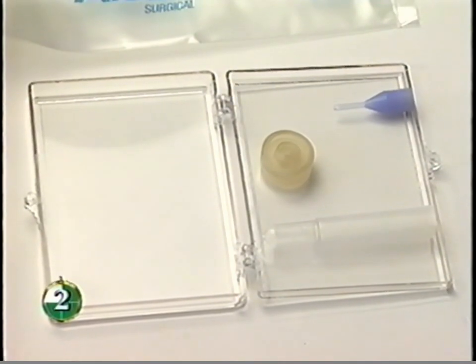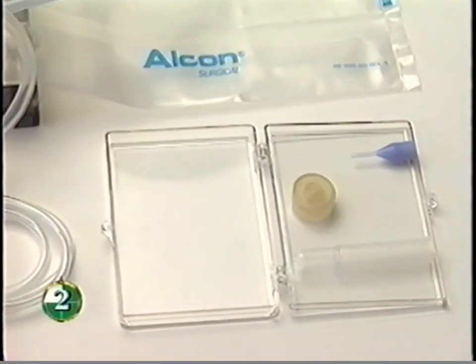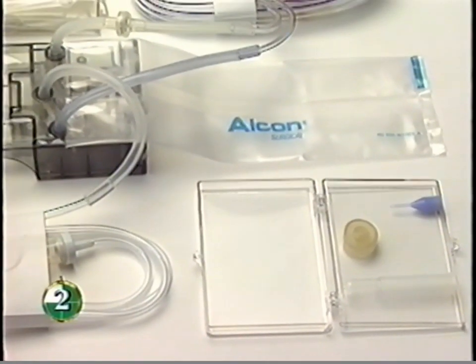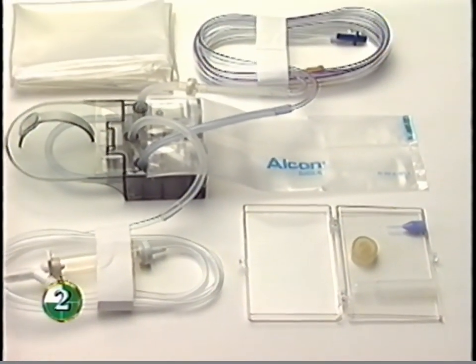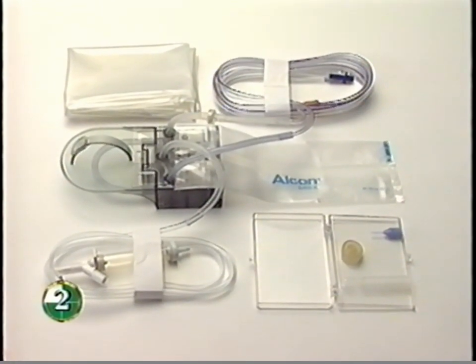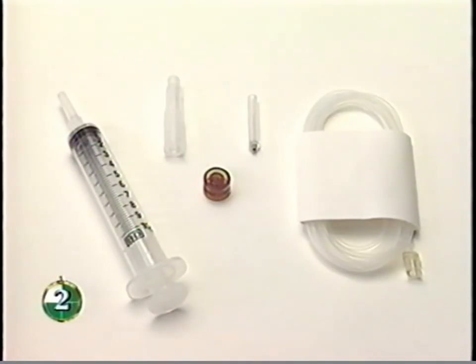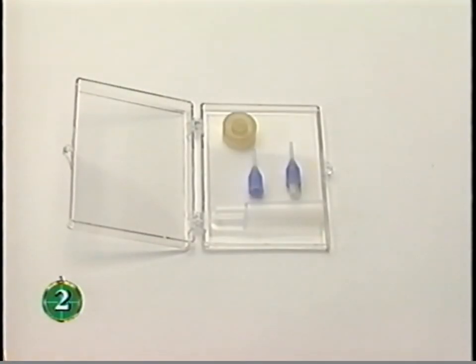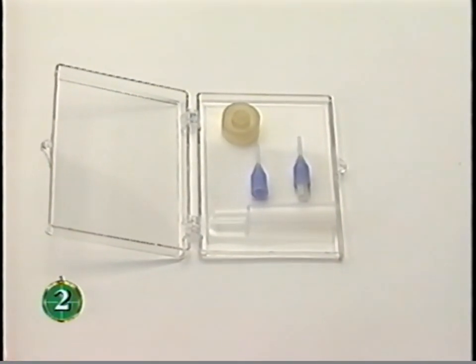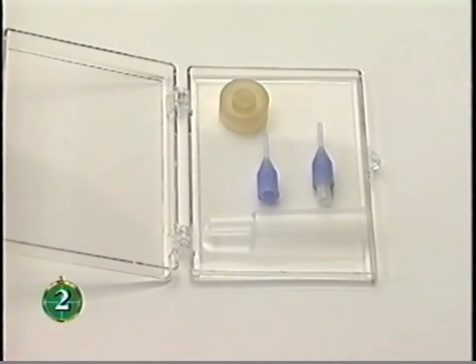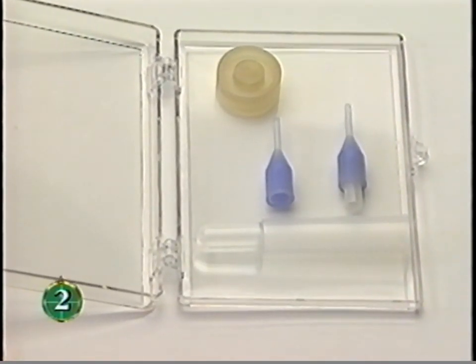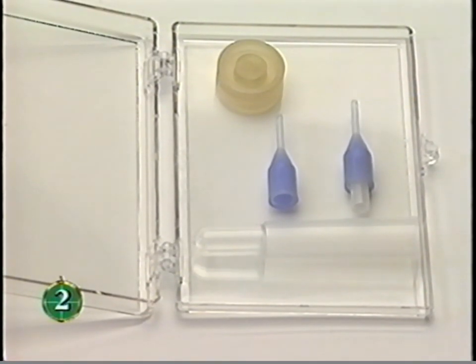Use the Series 20000 Legacy IA pack for performing extracapsular cataract extractions. The pack contains most of the same materials as the Turbosonics PEA pack, but does not include an ultrasonic tip. The special Hydrosonics tip and priming syringe are included in the Hydrosonics auto-injector accessory pack, along with a tip wrench, a vented test chamber, and 6 feet of tubing with luer fittings. A Series 20000 Legacy parts kit contains 2 sterile Turbosonics infusion sleeves, one with bubble suppression insert, a tip wrench, and a test chamber. It comes without tip or cassette.